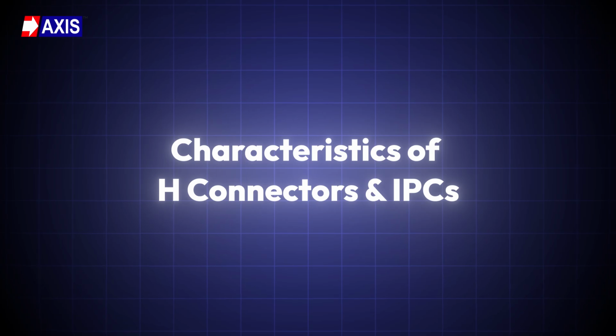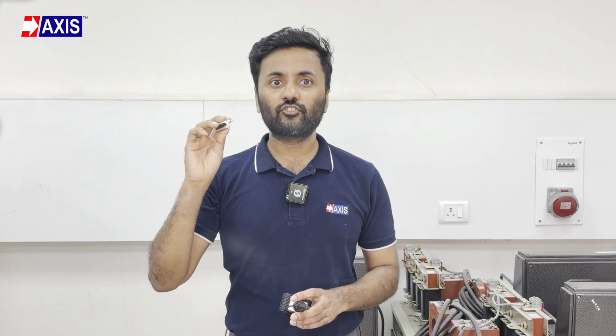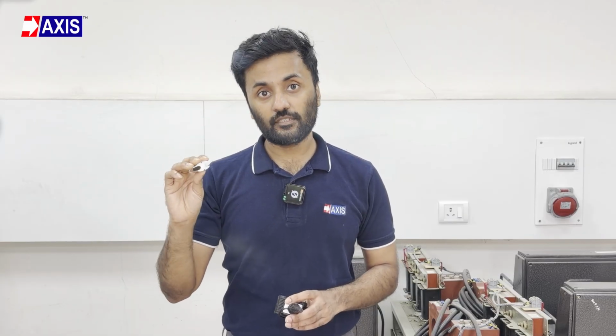But now let's move on. Let's understand the characteristics of both connectors. H connectors are built for permanent, heavy-duty joints. You use them for mainline splices where the connection carries high loads, and this demands maximum mechanical strength. An H connector compresses stripped conductors using a crimp, therefore you must strip the insulation before using it. You need a hydraulic or mechanical crimp tool, and these stripping and crimping steps make the installation slower. But once crimped, the mechanical strength is high. The compression joint will handle high tension loads.